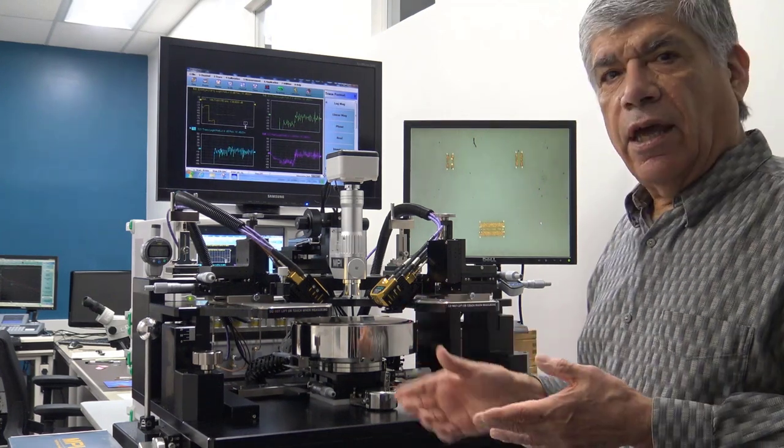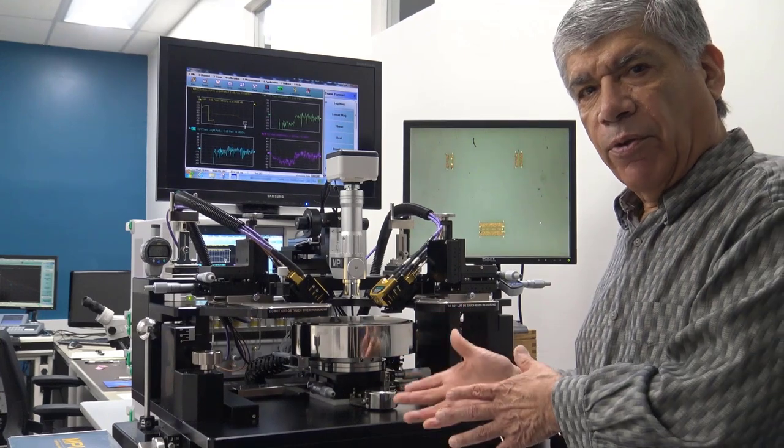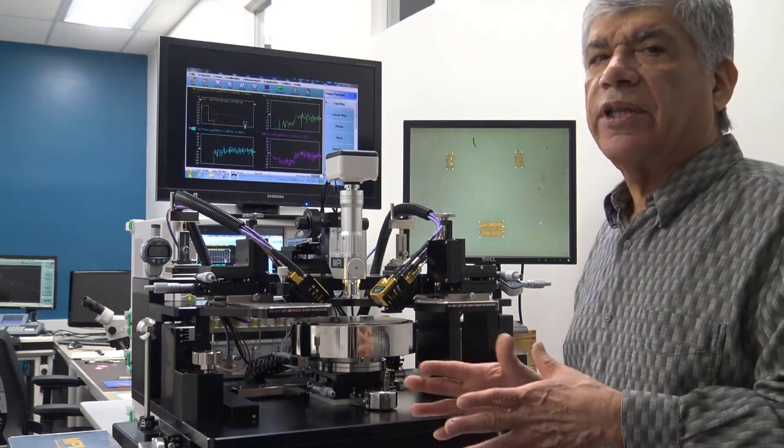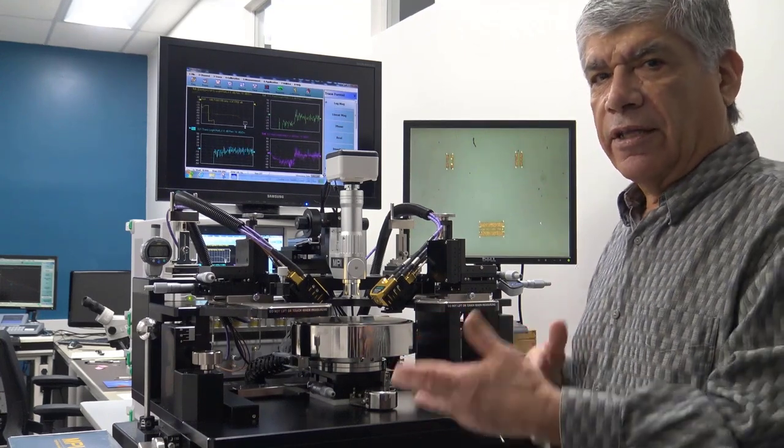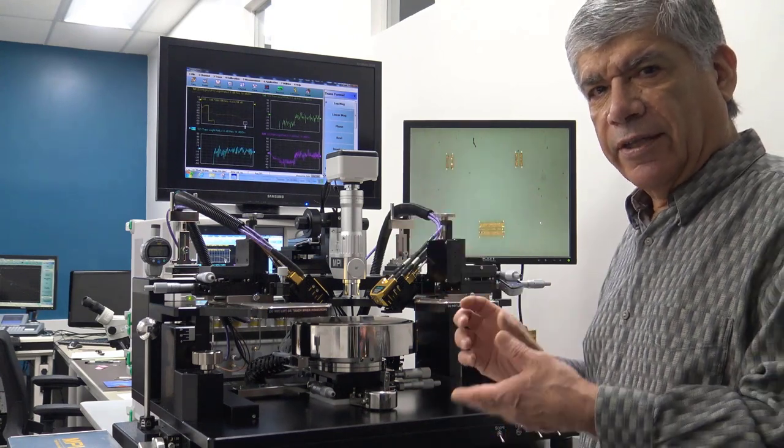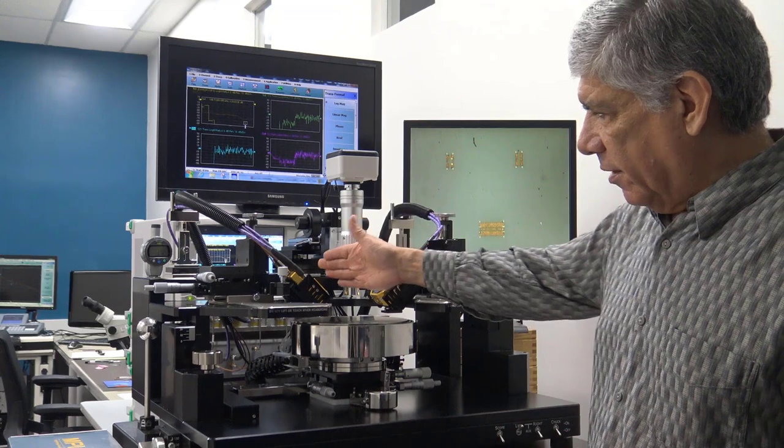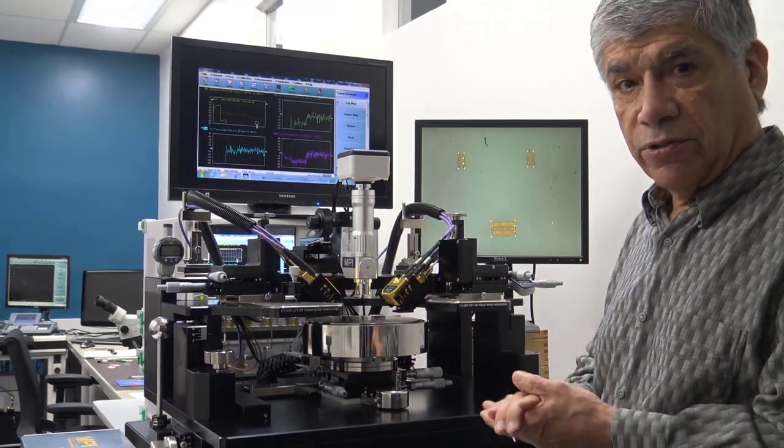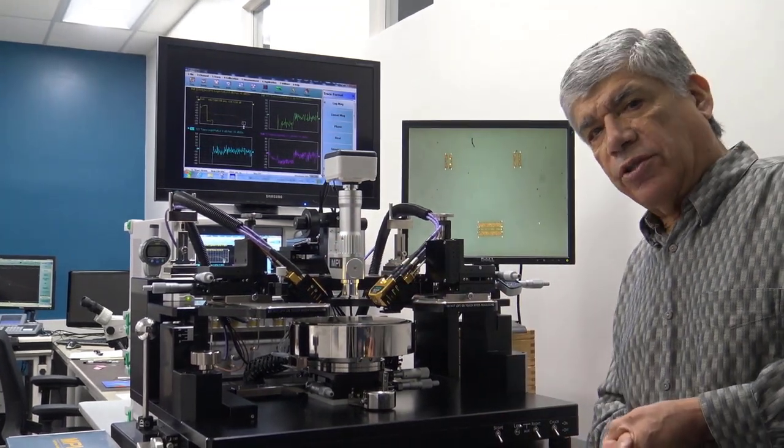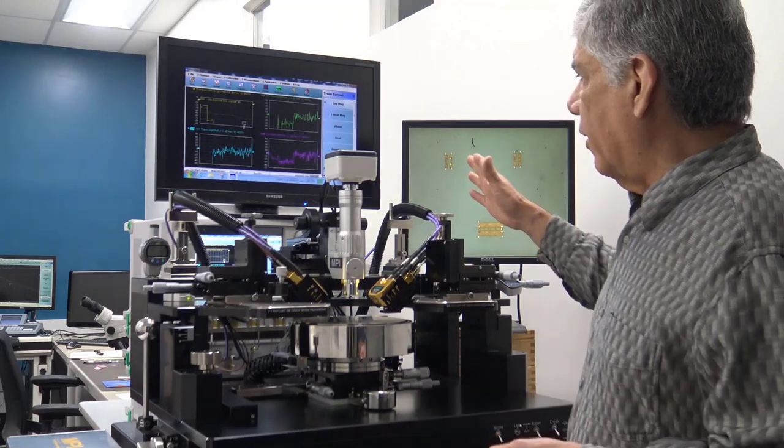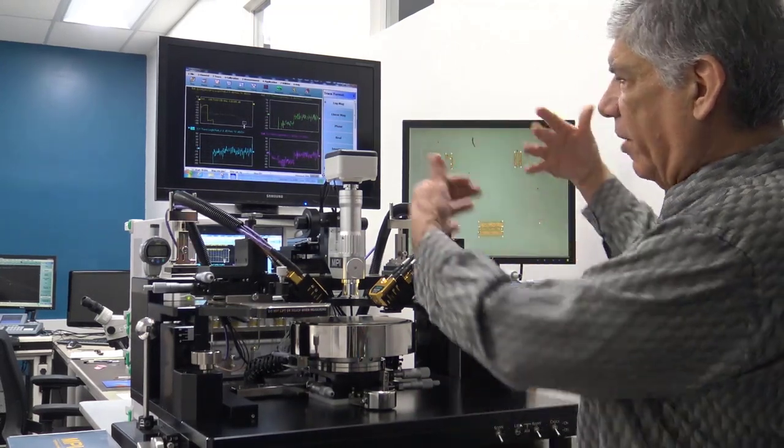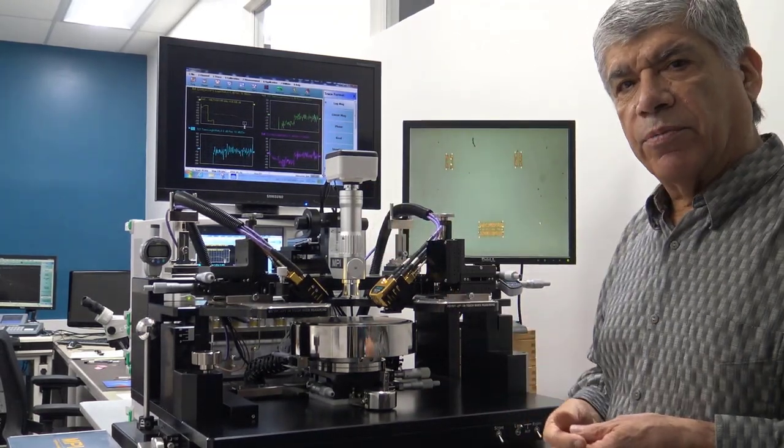The test set is very standard compared to our other broadband systems. So the 220 gigahertz system is not unique in the sense of the setup between the VNA and the test set as much as the uniqueness of the modules, the nonlinear transition line modules.